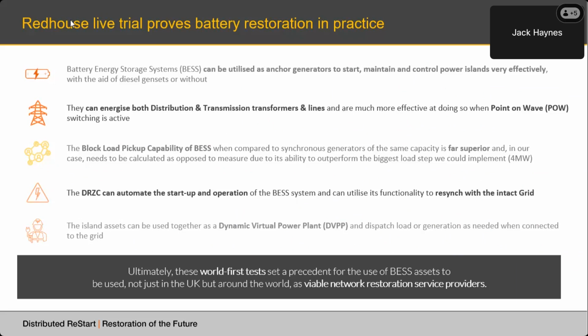We also measured the block load pickup capability, that figure I talked about earlier, so the instantaneous load that we can bring on in one go. So how many houses, essentially, can we turn on in one go with this device acting as the anchor whilst the island maintains stability. Again, I've got some more detail on a subsequent slide, but it was found to be far superior when compared to a synchronous machine of the same size.